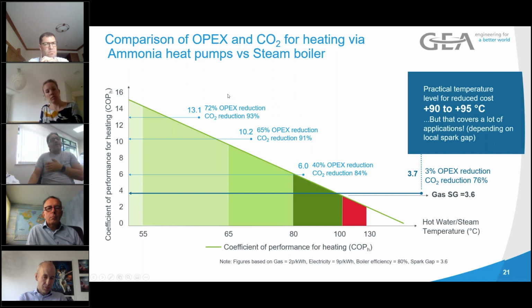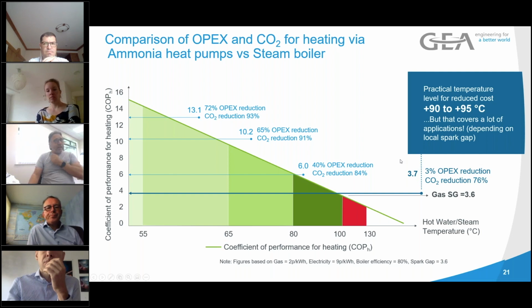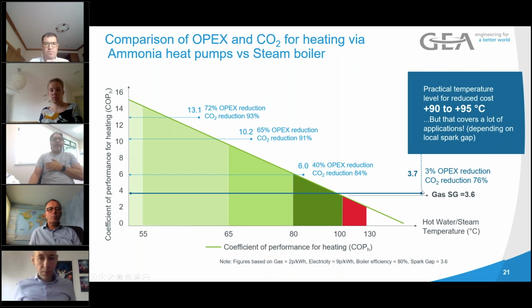So it's important, if half your heat is, let's say you've got a megawatt requirement at 65, you can do that with a COP of 10 and a carbon reduction of 91% compared with a boiler. Going up to 90, we do it with a COP of 3.7. You still have a very high CO2 reduction, but most of our clients have to see a return on investment. So we map this against gas. Depending on the region and the cost of electricity to gas, we get what we call a spark gap. As long as the spark gap means that our COP for heating is around about the same, most of our clients will go for this option, which limits the temperature of this technology.